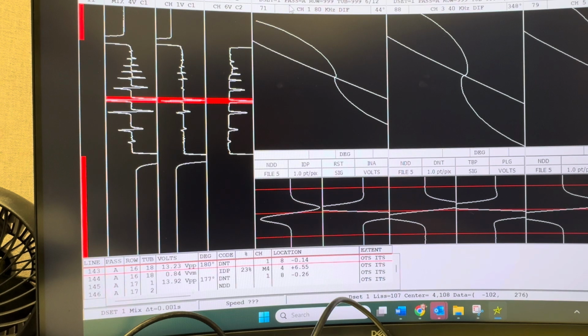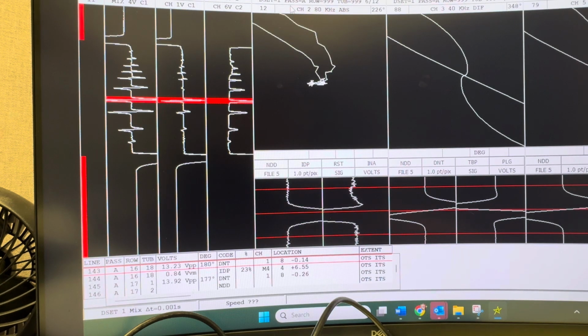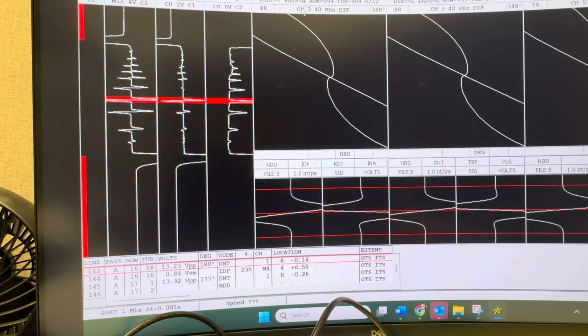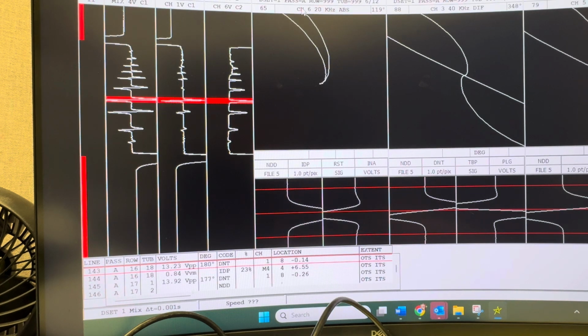That's one of the holes in your cal standard. But if you click over to the absolute signal, which is channel 2, 4, 6, and 8, that's your external comparison differential, notice how the differential and the absolute signals are occurring at the exact same place in time.